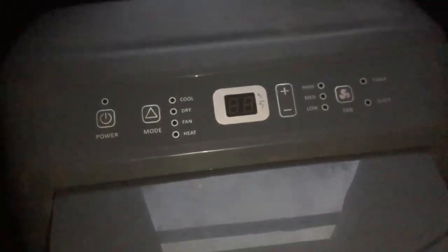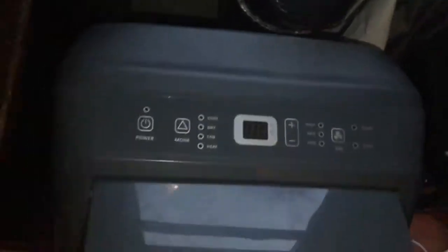Just be wary whenever you're running these things. Make sure you don't have something getting sucked up against the back of the coil, because it could freeze up that coil, and you don't want that freezing up. You also have to be wary of that condenser down there. If something gets sucked into it, that head pressure will skyrocket. Same thing in the heating mode.